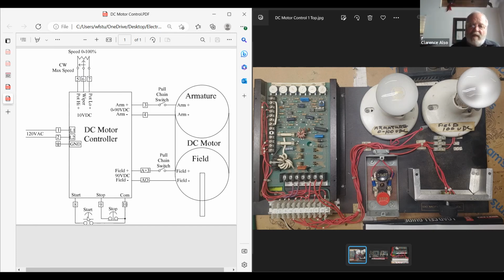And I press the start button, and then I'm gonna tell you my armature or my shaft is not turning. And I check here at my outgoing terminals for my armature. I'm expecting it to read 45 volts and I'm getting 0. So that's a bad reading, is that right? If I'm getting 0, and I should have 45, because of why?